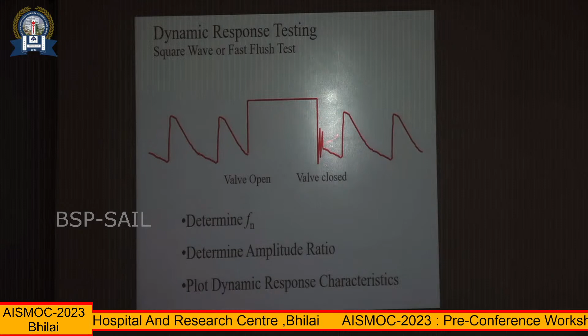So how you do it is, again, you do a fast flush test or the square wave test, whatever we call it. When you open the transducer and you release it, you will get the resonance from the transducer, because the bag is pressurized and the column sees a higher pressure once you activate the flush. Once you release it, there is the inherent resonance of the system, which will give you this waveform.